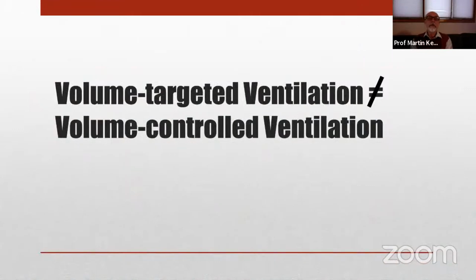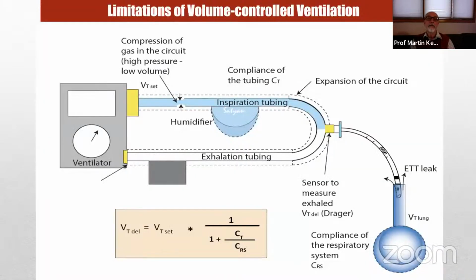So I just want to point out the difference between volume controlled ventilation and volume targeted ventilation. Volume controlled ventilation is the adult style of ventilation, where a fixed tidal volume is injected into the proximal end of the ventilator circuit. In other words, volume control ventilation controls what enters the patient's circuit. It does not control what enters the patient's lungs. That's an important distinction. In larger subjects without an endotracheal tube leak, this works just fine because the lungs are large and more compliant than the circuit.